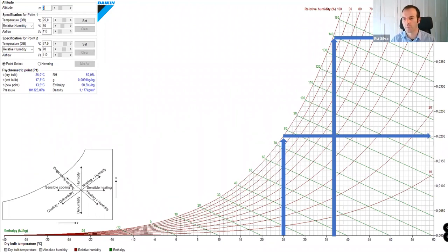And these are numbers that are critical for our process in our setters and hatchers, because this will be the amount of water that you can control for your egg weight loss on your exhaust side or inside your machine. And 25 is a typical number that we consider for your inlet to the setter or hatcher room, okay?